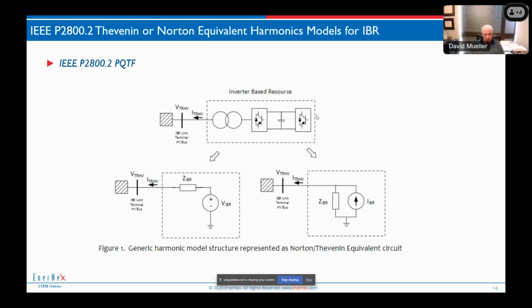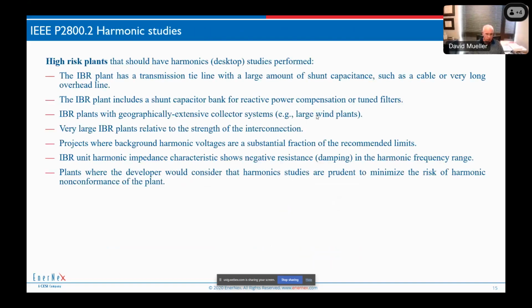Harmonic studies are all about getting the right answers. If we get too conservative answers, we end up putting harmonic filters in everywhere. And actually, we find from experience we don't need harmonic filters most of the time. We've also talked quite a bit about when we should do harmonic studies. Should we do harmonic studies for every IBR plant, or are there high risk plants? And right now the draft has settled on high risk plants.